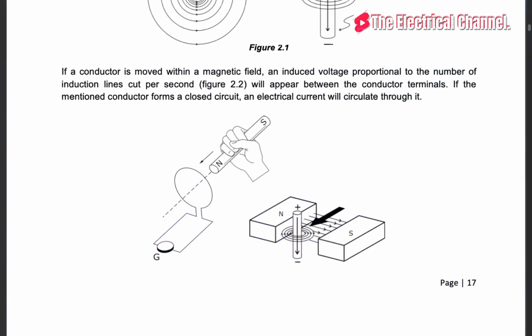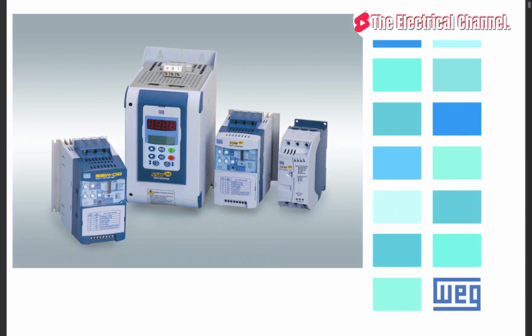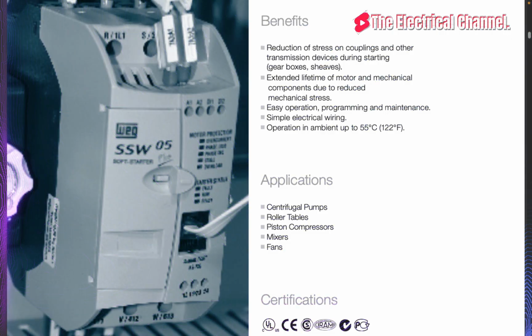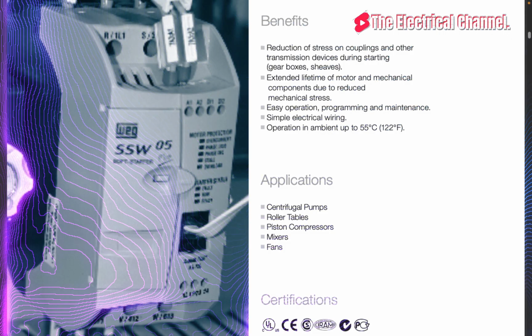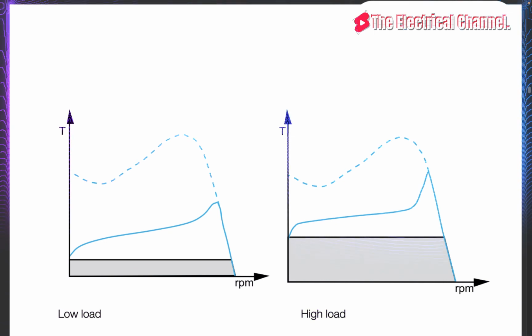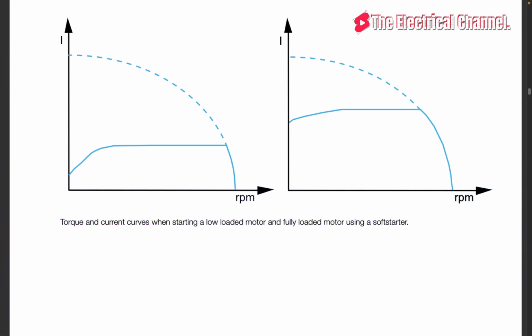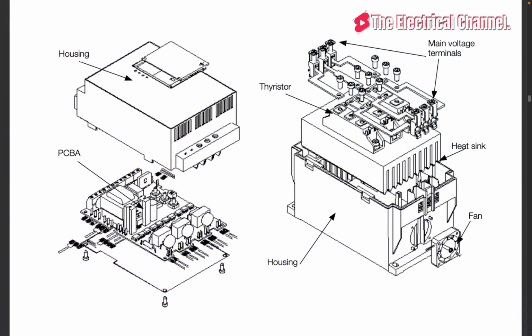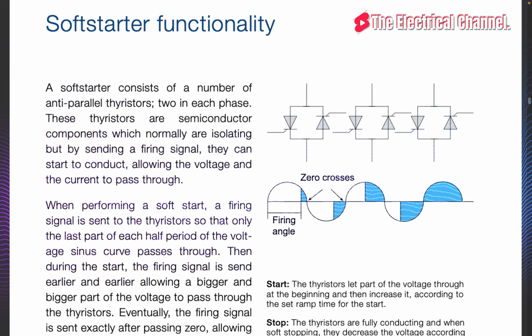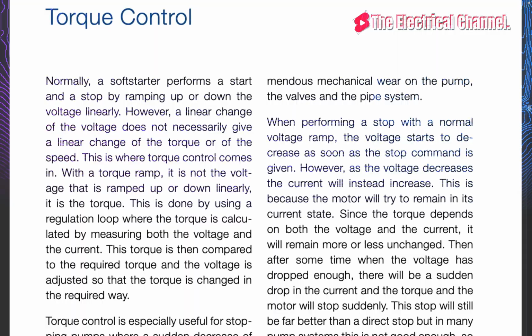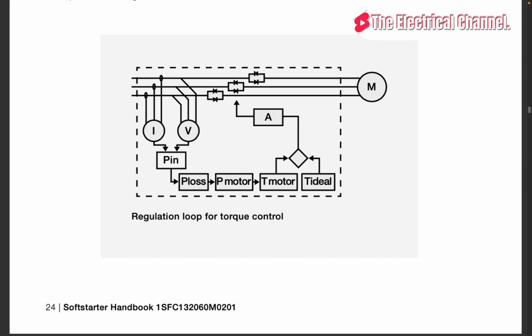Some two-phase control softstarters create DC components. When ramping up and down by controlling only 2 phases, a DC component will be created which will have a braking effect during the torque and create a very noisy, bad start. Only very few two-phase control softstarters on the market are equipped with some sophisticated algorithm to eliminate this DC component.